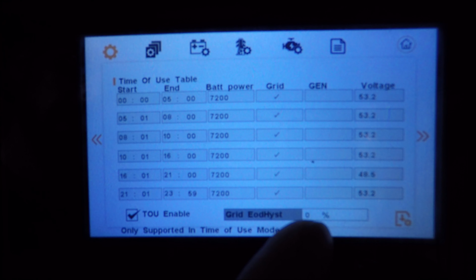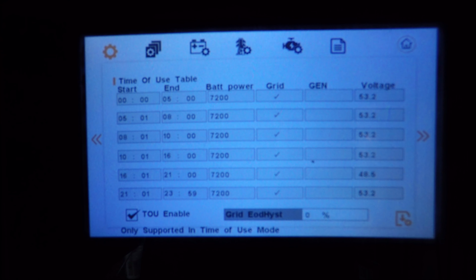We also have grid charge enabled for all of the time slots, and battery power. So this is the total amount of watts that the battery can produce. Now, keep in mind that how you would figure what the watt capacity is of your battery is, your batteries are generally 51.2 or 48 volts. Mine are 48 volts. They are capable of producing a constant discharge of 100 amps for a total of 4,800 watts. That's for one battery. Now, since I have 4 batteries, I can produce significantly more than that, but I'm mitigating the amount of stress that comes out of the batteries for this charge cycle. So I've chosen to just leave it at 72. I'm going to hit next.